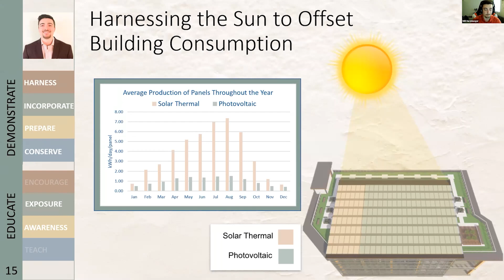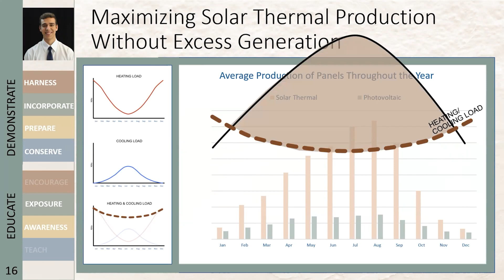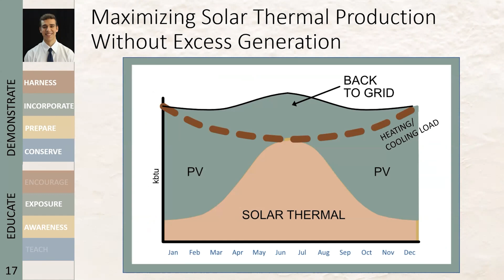Both types of panels generate the least energy during winter and the most during summer. Our building loads follow the opposite pattern, requiring the most energy in winter when production is lowest. If we sized the solar thermal panels to cover the winter load, there would be a massive surplus of heat in summer that couldn't be sold back to the grid since it's in the form of heat. Instead, we sized the solar thermal panels to cover the summer load, and sized the photovoltaic panels to cover most of the winter load, so excess generation can be returned to the grid as electricity.